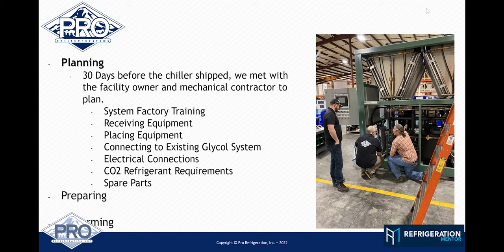The first system we fired up was for a dairy farm operating at about 35 degrees Fahrenheit for their set point. With this facility and application, we operated at 28 degrees Fahrenheit. So we have a heavier glycol concentration for a colder evaporator, but we also have to protect against cold ambient temperatures so that if pumps shut off and we have stagnant fluid, we don't freeze. In this case, they're running about a 45% glycol concentration - it's really thick stuff.